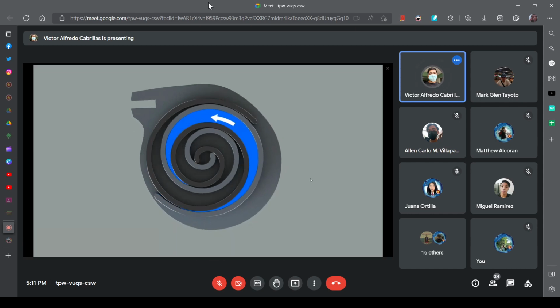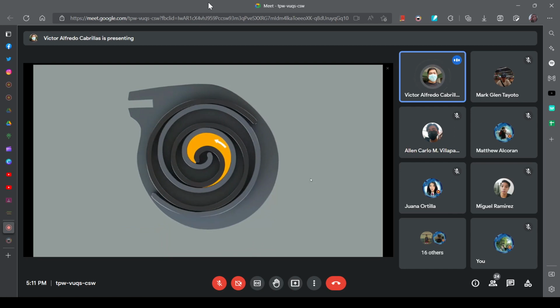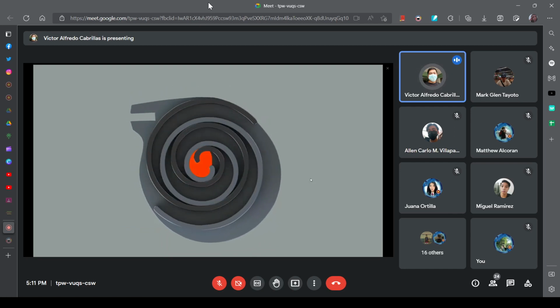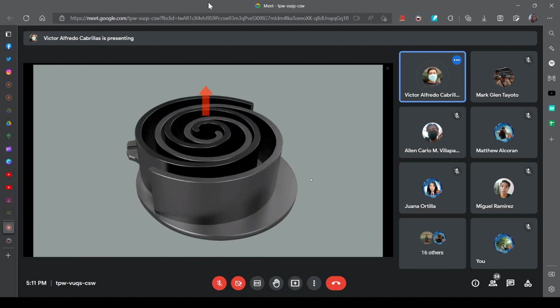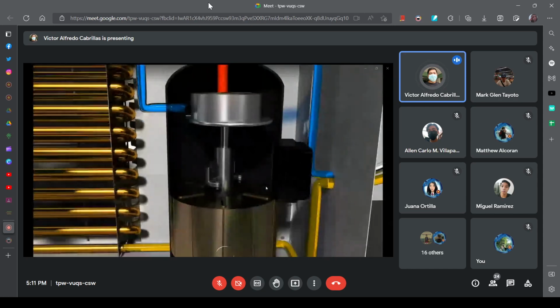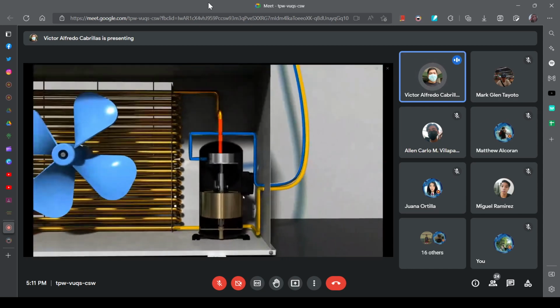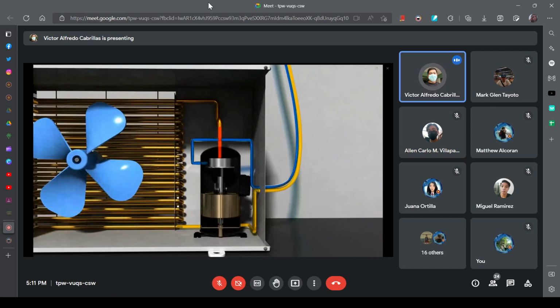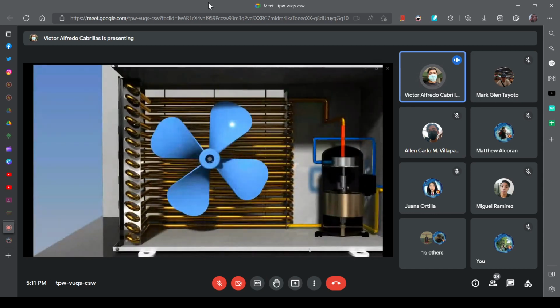Space becomes crowded. As there is less space now, gas becomes more compressed and is discharged from the middle of the scroll in a compressed state. The reason for using such a type of compressor is the efficiency of space utilization. This type of compressor allows the machinery to become smaller in size and reduces noise as well as vibration. Compressed air is then sent to a condenser to be pressed into liquid.